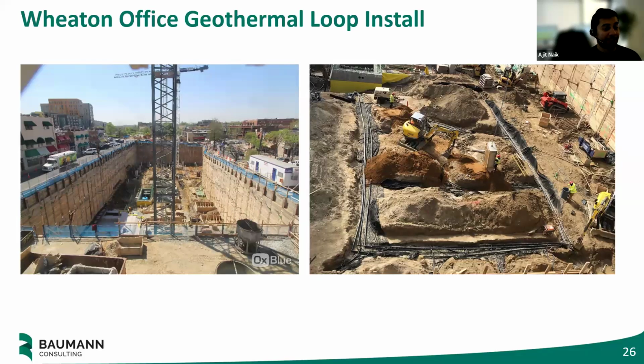So they were seeing the flex and thinking, 'Oh my gosh, there's a leak,' and they did it four or five times before we said, you really have to read the spec. Once they added a little more water and maintained it, they were able to comply. So there was no leak—they just weren't accounting for the letter of the law and how that test is written. It's super important that it's specified properly.